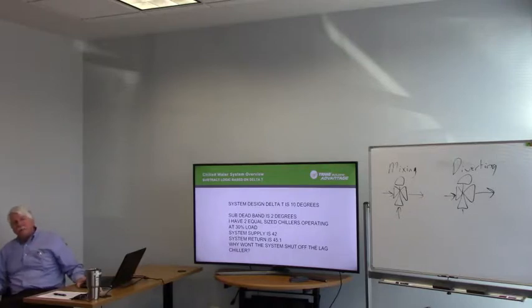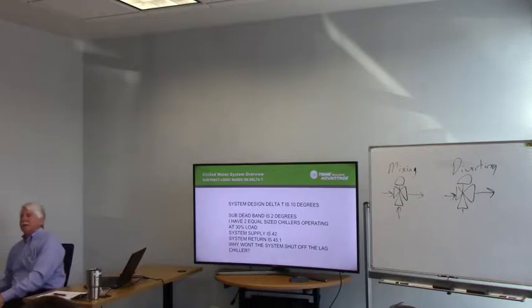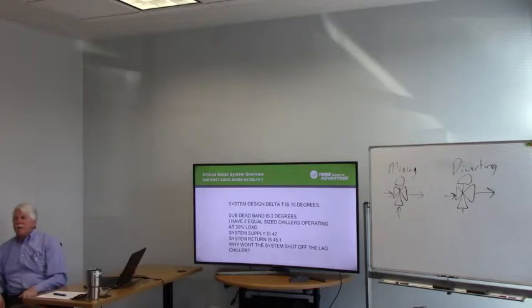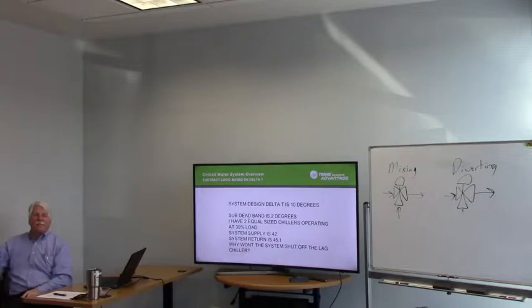Okay, last math question before lunch. This has to do with adding and subtracting logic in chiller plant control. Now, chiller plant control has one mission in life: I need to make water leaving that plant at a temperature. That's my primary goal. And no matter what's going on with bypass lines and everything else, my goal is to maintain the system sensor at set point.